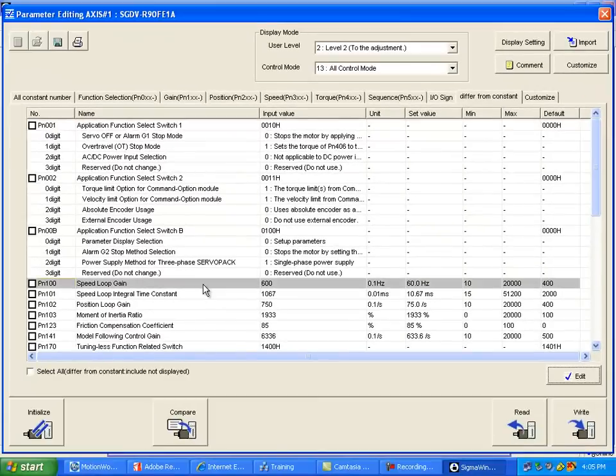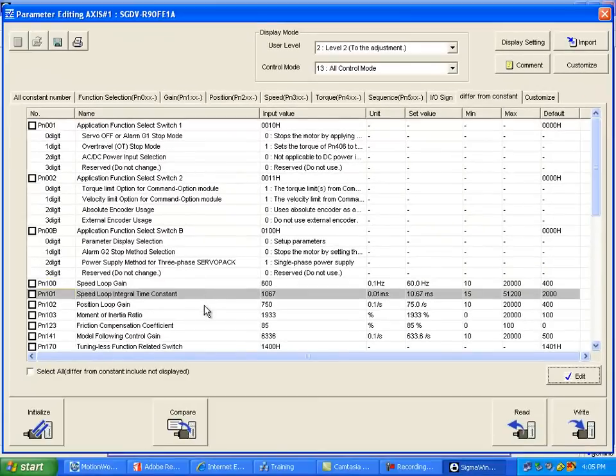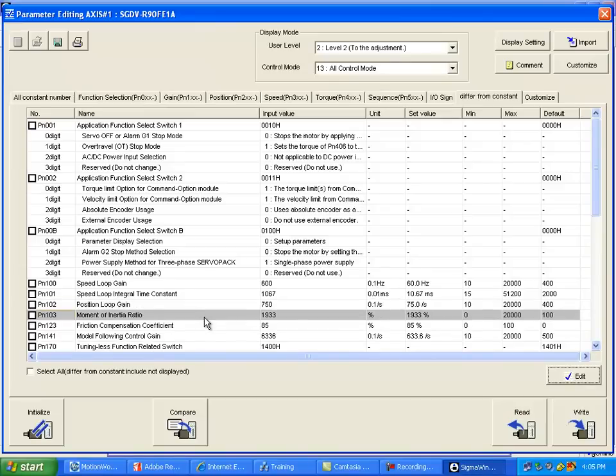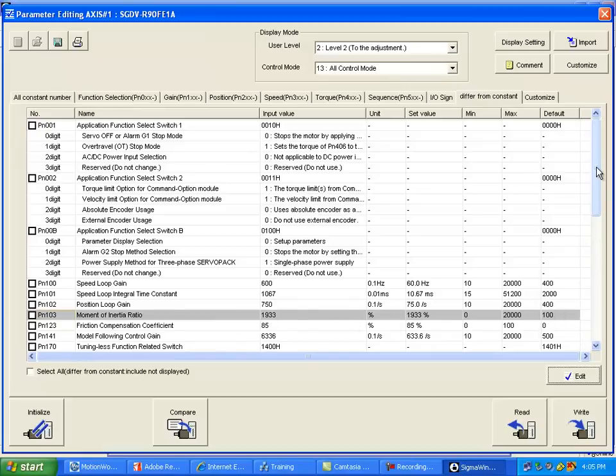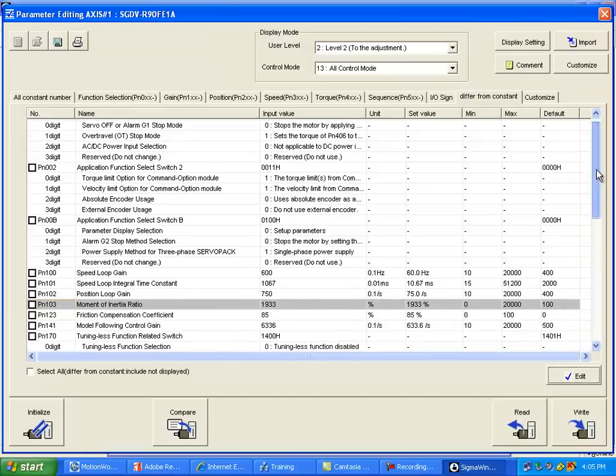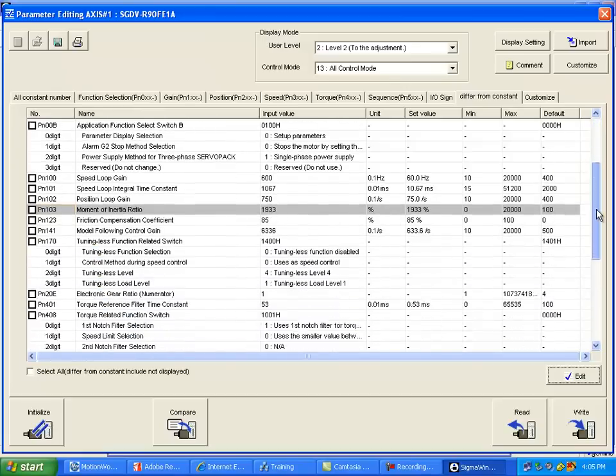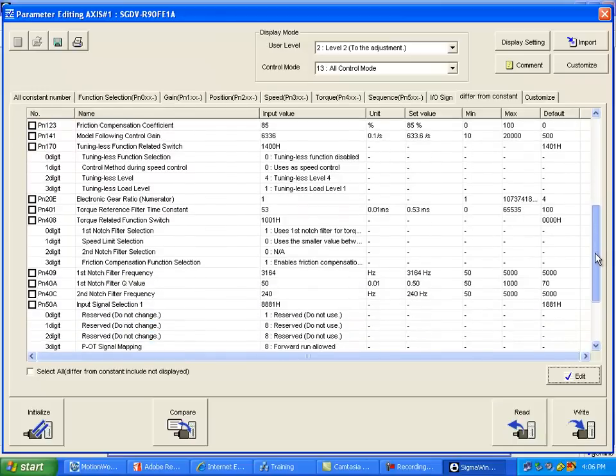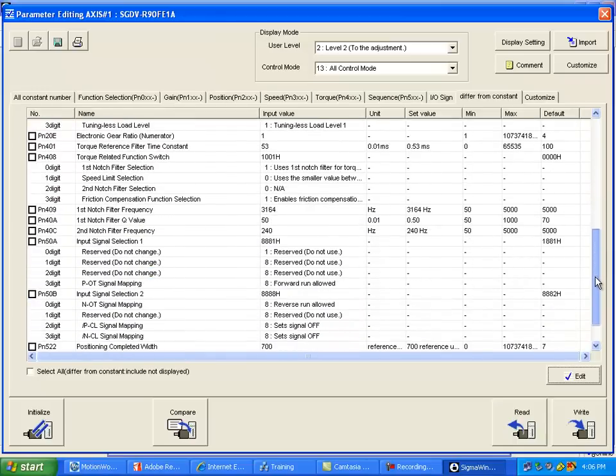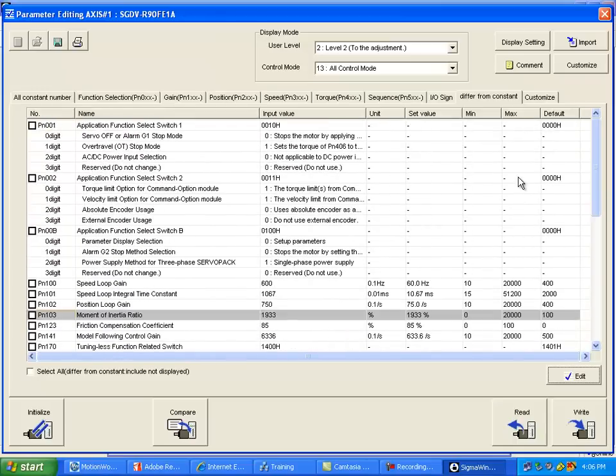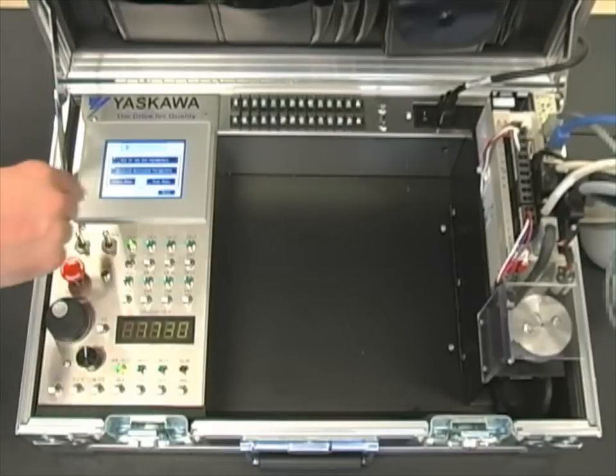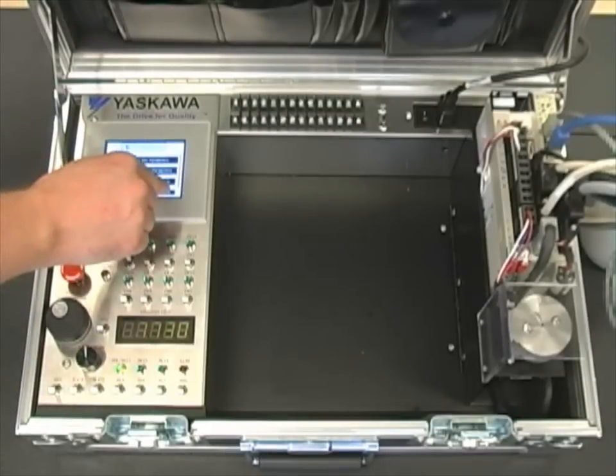The main parameters we changed are PN100, 101, 102, and 103. You can see where the current value differs from the default value. There are additional tuning parameters that were changed as well as you scroll down, but we wanted to highlight the main four there. Now let's select Back to exit out of the tuning mode.